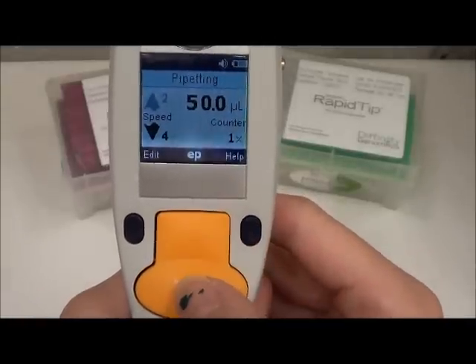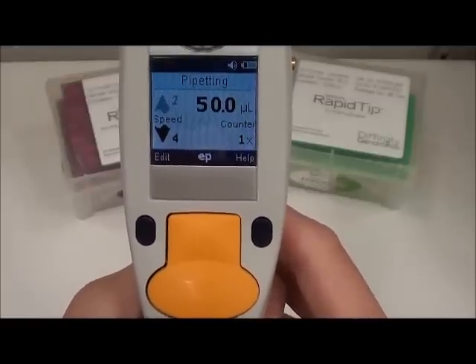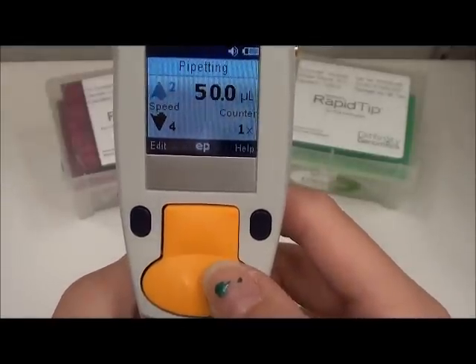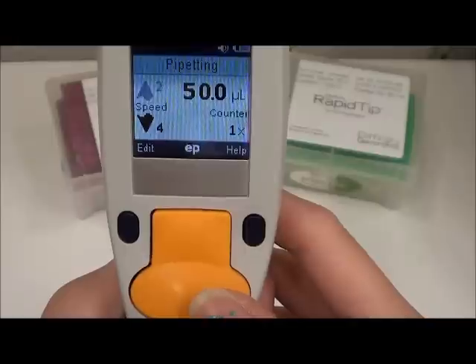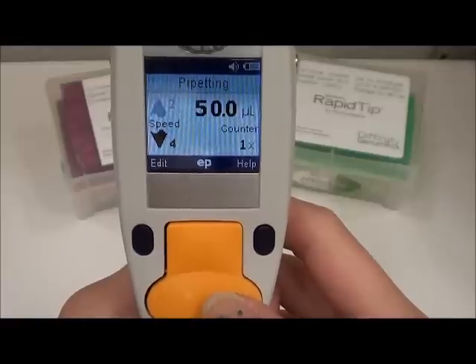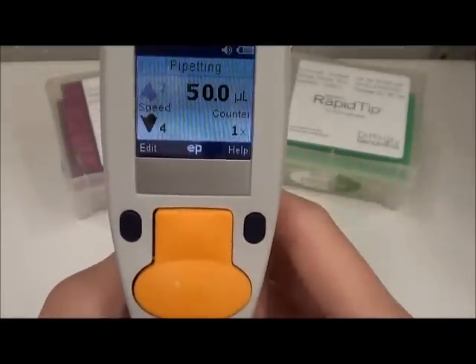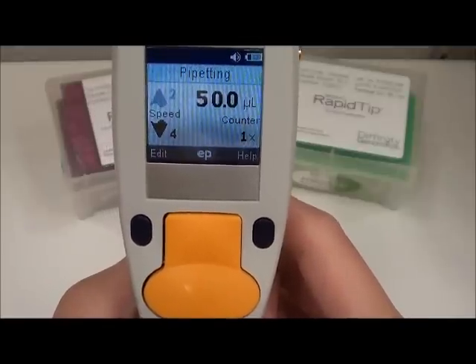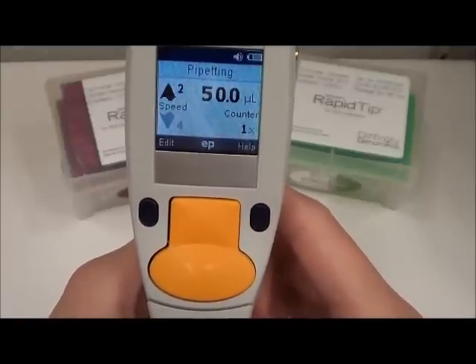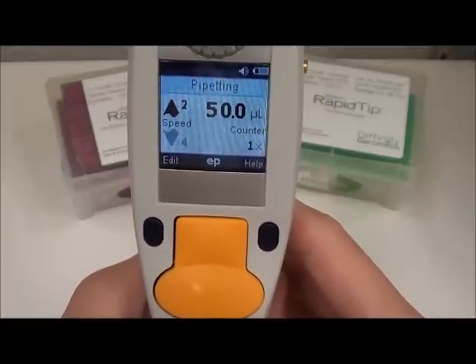The counter went to 1 because I did one cycle of up and down. One thing this pipetter does on its own that you'll want to know about: if you have already hit the dispensing button and you hit it again, it will do a blowout function. This is really good for the last cycle of your one-minute purification time. But if you hit it in the middle, it will blow out your sample and also suck back in to get back to a 0 microliter volume. So if you don't want to mess up your pipetting during that minute, stay away from the blowout function. But if you want to use it at the end, we highly recommend it — it helps get the extra volume that might stay behind in the tip out into your sample.